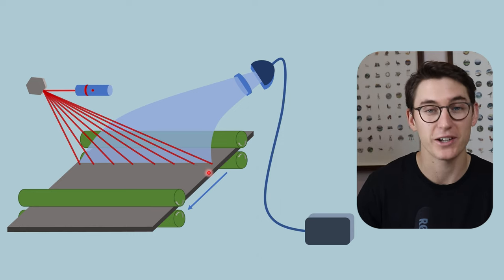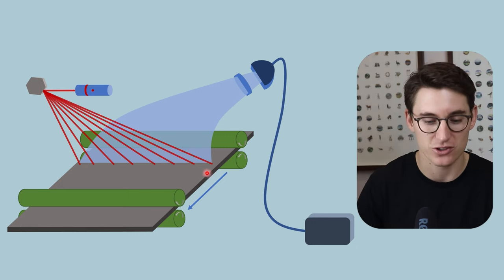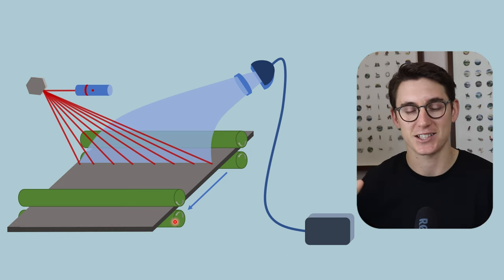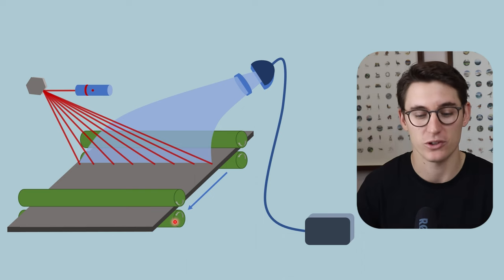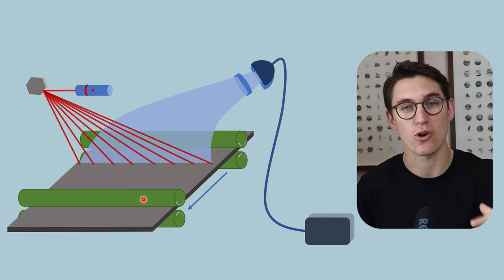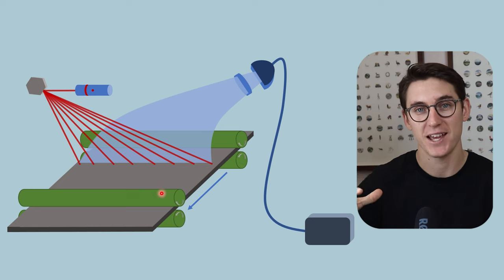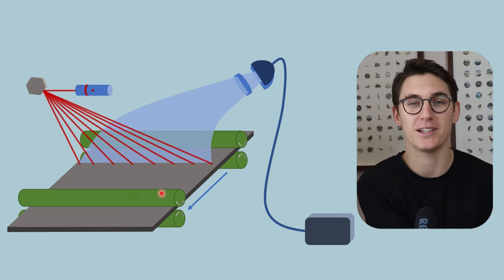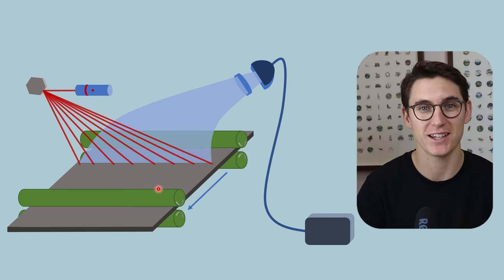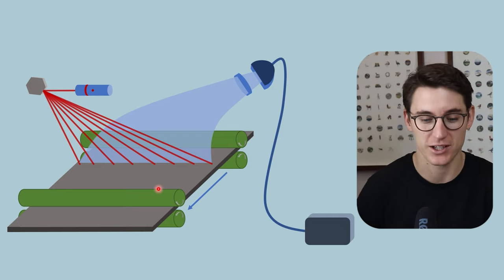The computed radiograph can actually be read out multiple times — not all F-centers are released on the first scan, so each time we read it out the signal gets slightly less. We can read this two to three times before losing all of those F-centers. If we want to clear the cassette completely, we shine a bright white light onto it, releasing all electrons from the F-centers so the cassette can be reused. It is important to clear the cassette before taking another radiograph, otherwise we'll get a superimposed image of both radiographs.